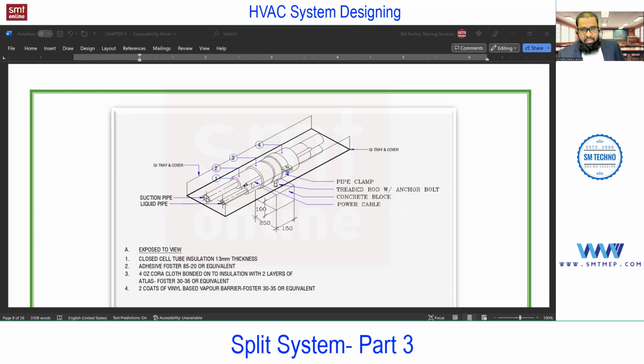outdoor. So in some models, the power connection is to the indoor, and from there the supply of power goes from indoor to outdoor, or in some models, the main supply is to the outdoor and the indoor will receive the power from outdoor. So mostly in actual practice in the present market, you will find the models with the power supply to the indoor and from indoor the supply to outdoor. Okay, so it can be in reverse also as per the model, but commonly indoor to outdoor. So that's the reason we require this cable also.